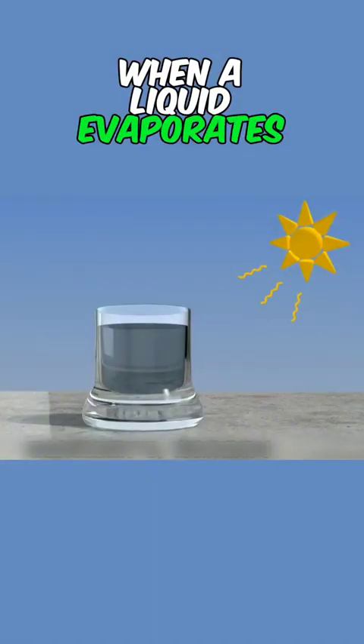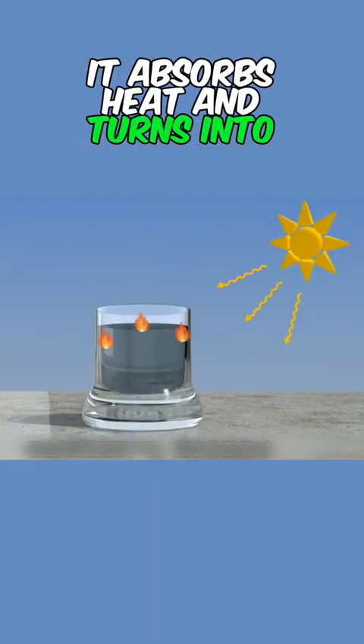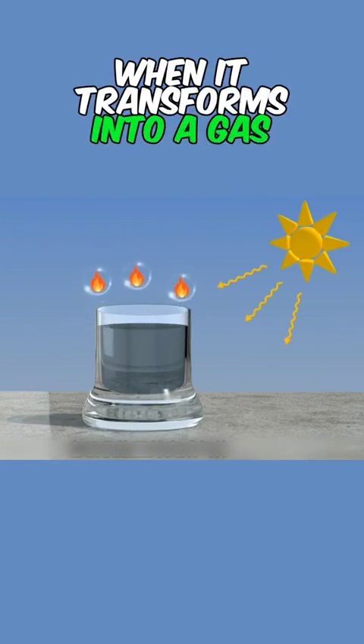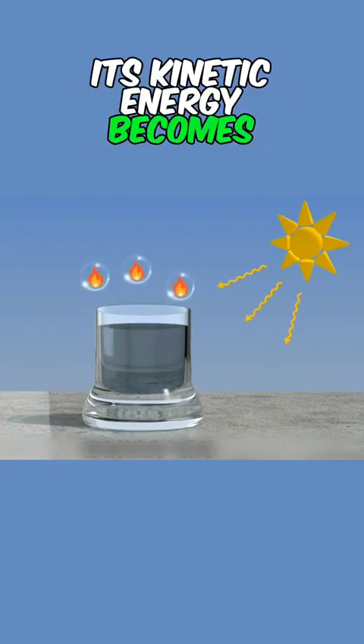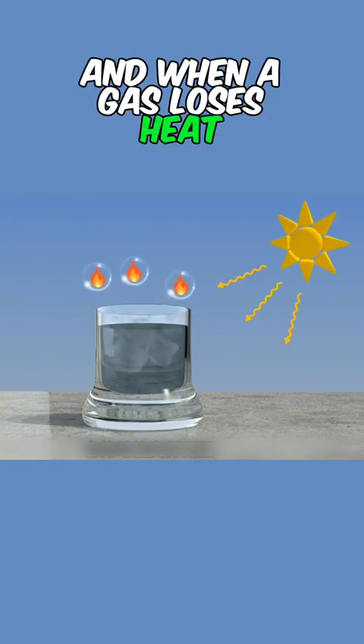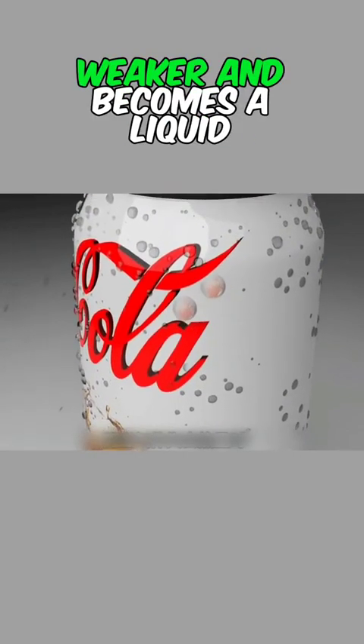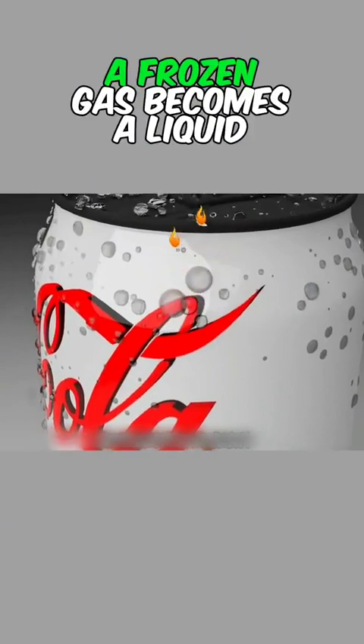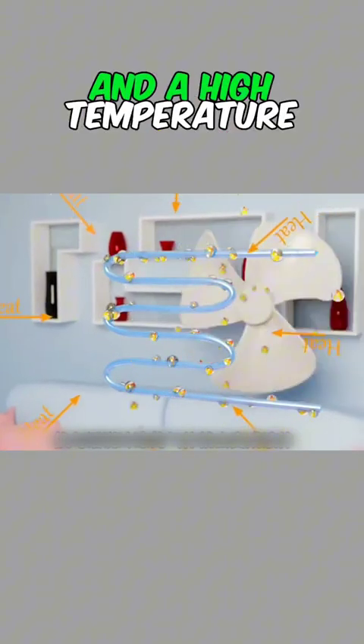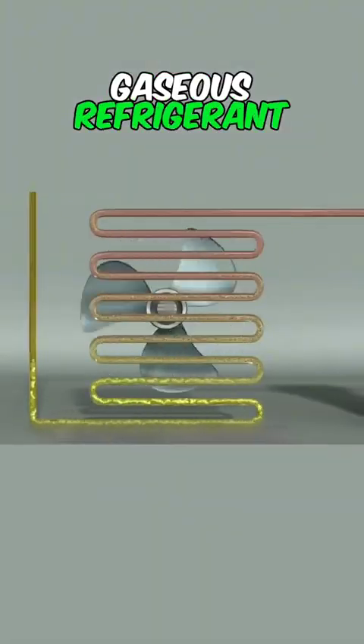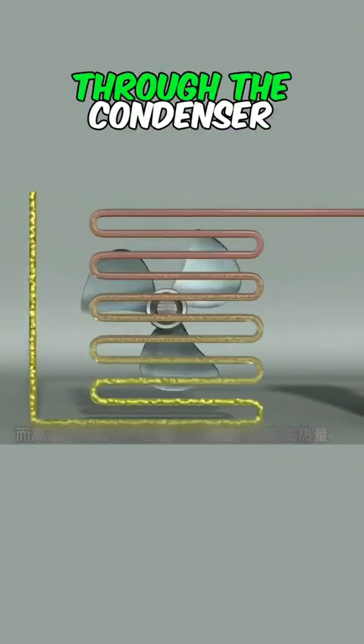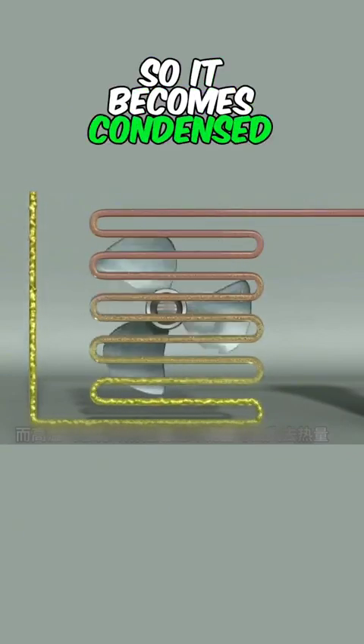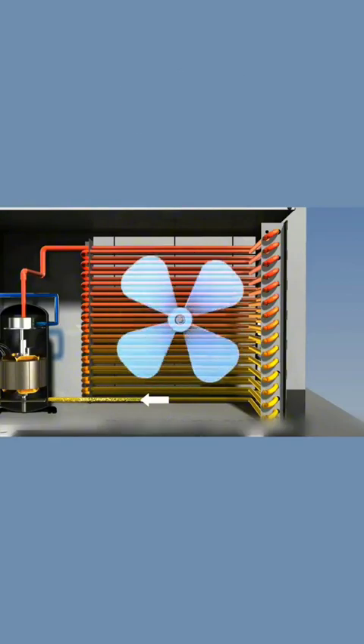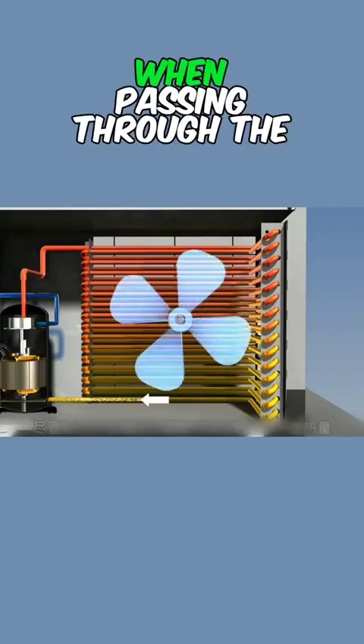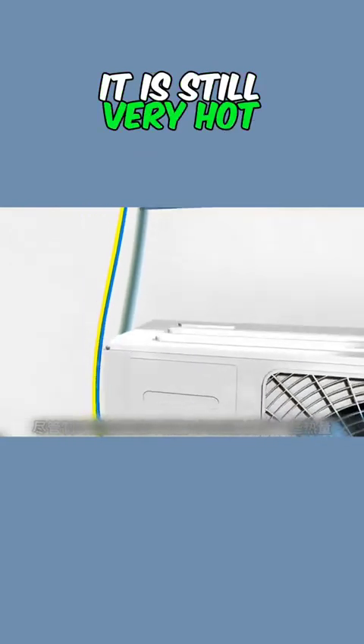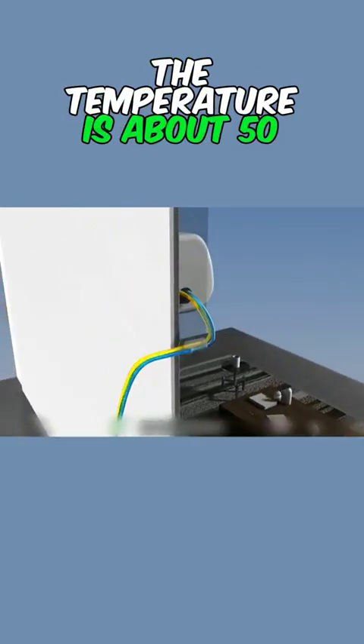When a liquid evaporates, it absorbs heat and turns into a gas. When it transforms into a gas, its kinetic energy becomes stronger, and when a gas loses heat, its kinetic energy becomes weaker and it becomes a liquid. In other words, a high temperature, gaseous refrigerant loses heat while passing through the condenser, so it becomes condensed and becomes liquid at the outlet. Although the refrigerant has lost some heat when passing through the condenser, it is still very hot. The temperature is about 50 degrees Celsius.